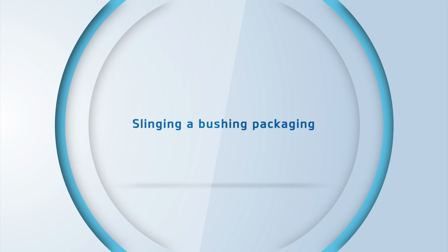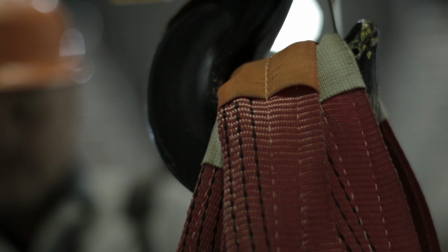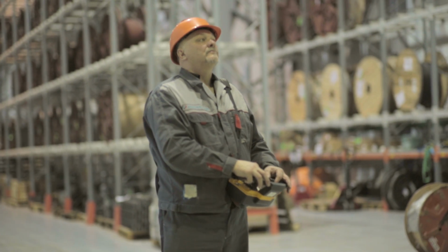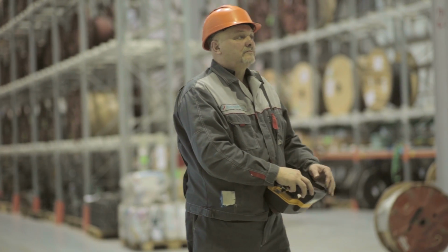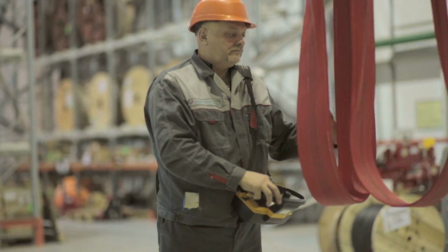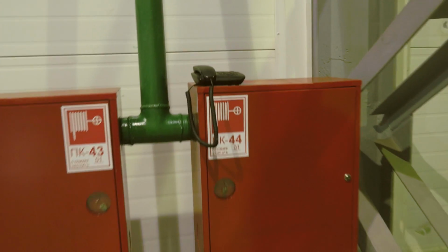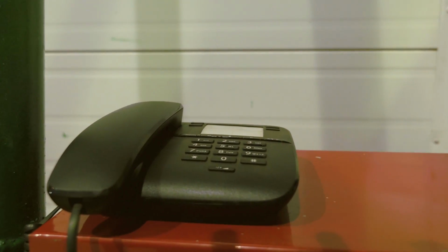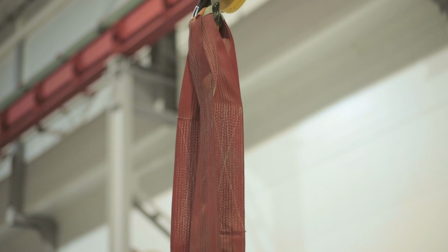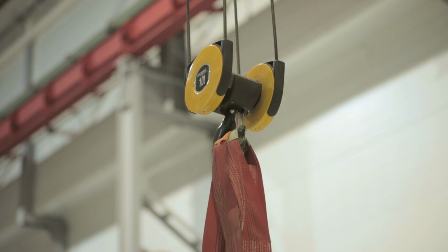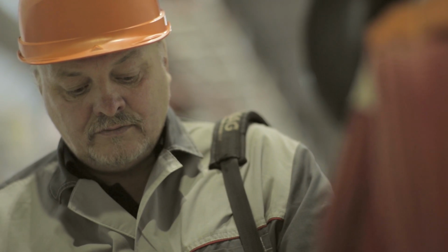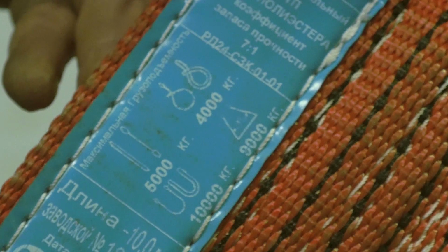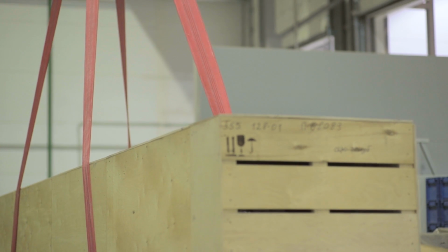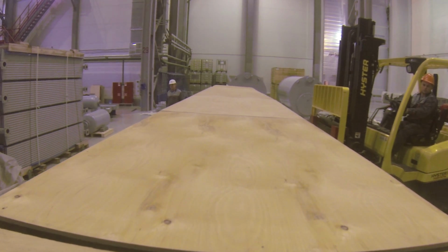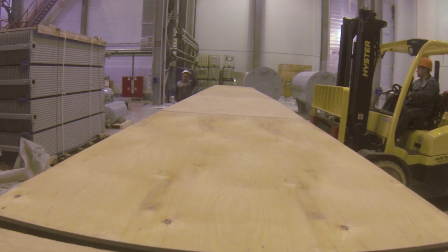Slinging a bushing packaging. Let us proceed to the installation of a high-voltage bushing, which starts with the loading-unloading operation. Before you start unpacking a bushing, make sure that the facility has operating means of communication, the unloading machinery can carry the weight of the product and is in good order. Cargo wire ropes meet necessary characteristics, are certified and intact. Packaging and bushing slinging and hauling must be done by individuals having necessary health and safety certification.